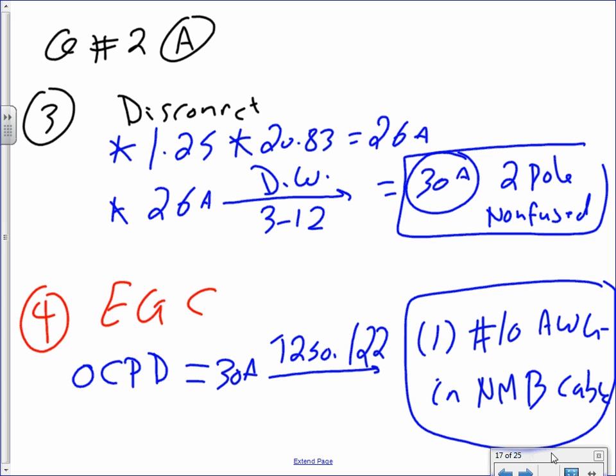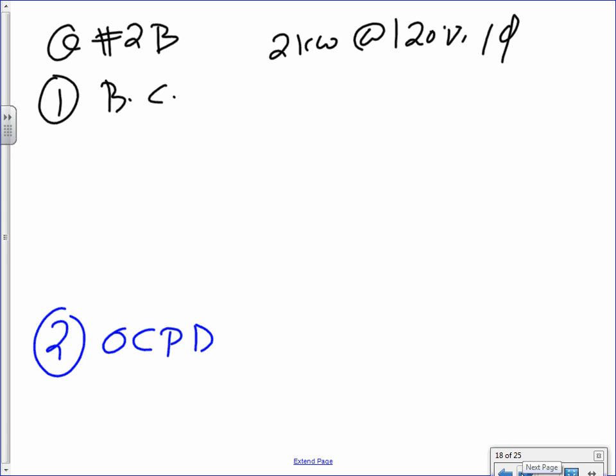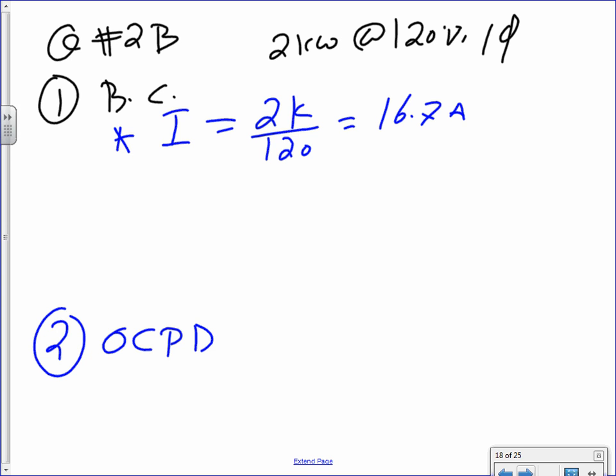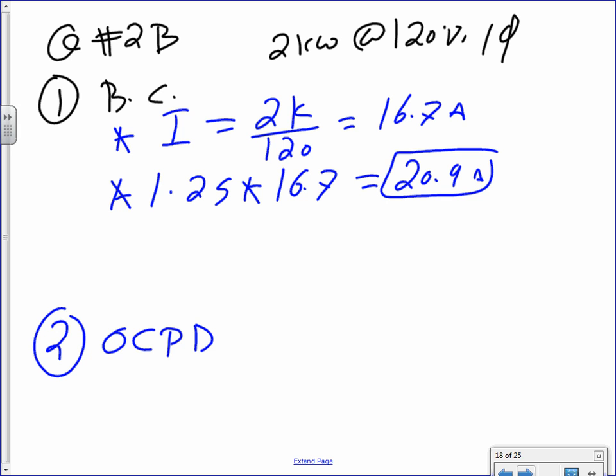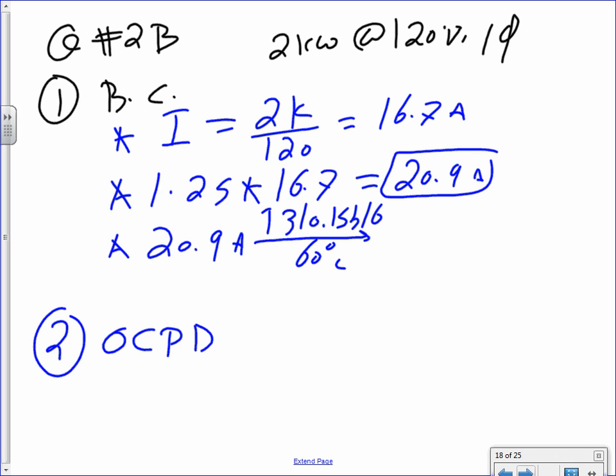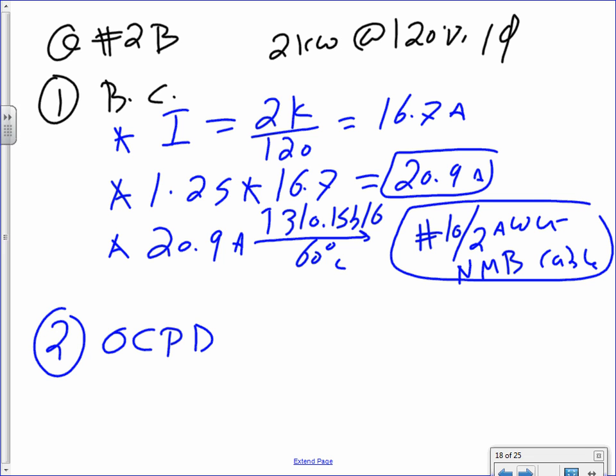Okay. Let's go to 2B, guys. Now we're repeating ourselves, really. For 2B, you have to find now the current for this guy. I have 2K divided by 120, which will give me 16.7 amps. Then 1.25 multiplied by 16.7 amps gives 20.9 amps. If you take 20.9 amps to table 310.15 B16 under 60 degrees, that will get you number 10 AWG in an NM cable. Done. See how easy that is?